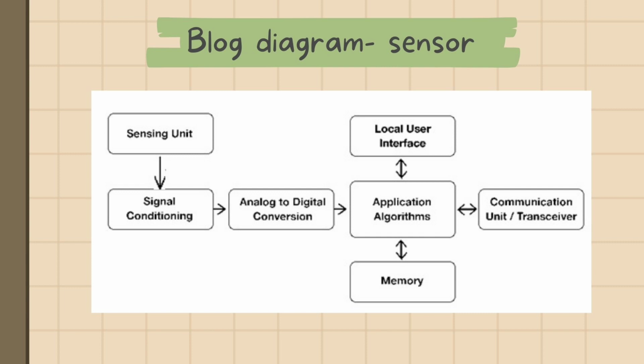For the sensing unit, this unit detects the changes in physical parameters and generates an electrical signal equivalent to its signal. Next, for the conditioning unit, the signal conditioning unit controls the signal to meet the necessities of the next level operation without losing data. Next, the analog to digital converter. The ADC converts the signal from analog to digital format and sends it to the microprocessor.